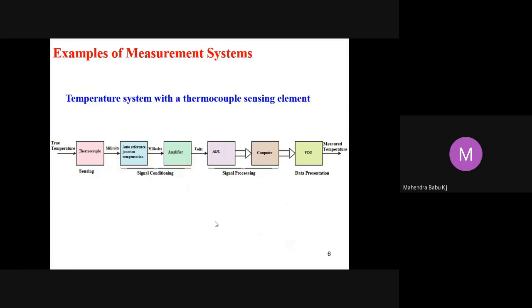When you come to a temperature measurement system with a thermocouple sensing element, we have a block diagram like this, where the figure shows the temperature system with a thermocouple sensing element. The first element is the sensing element, where we use a thermal sensor like a thermocouple, which gives a millivolt output. The signal conditioning consists of a circuit to compensate for changes in the reference junction temperature, and an amplifier. The voltage signal is converted into a digital form using an analog to digital converter. The computer corrects for sensor non-linearity, and the measured value is displayed on the VDU, the visual display unit.